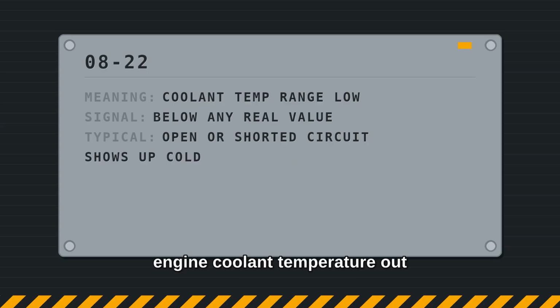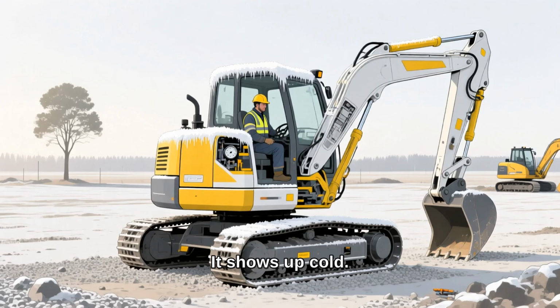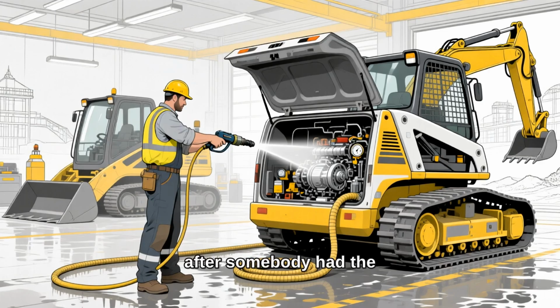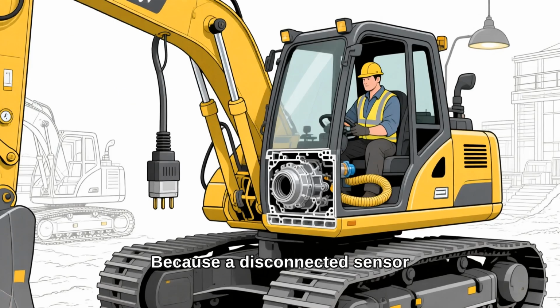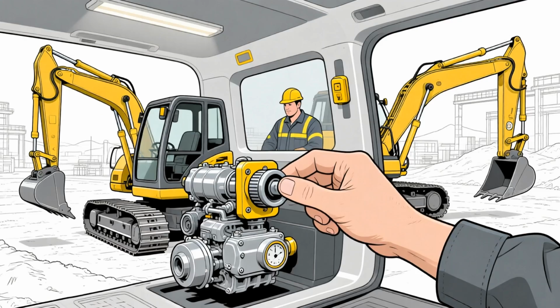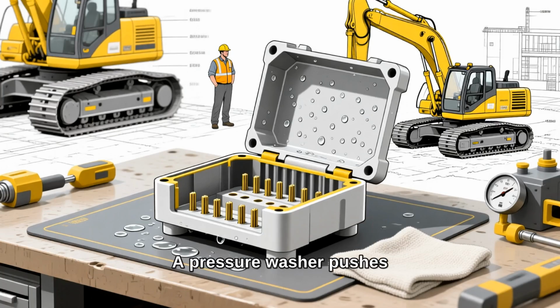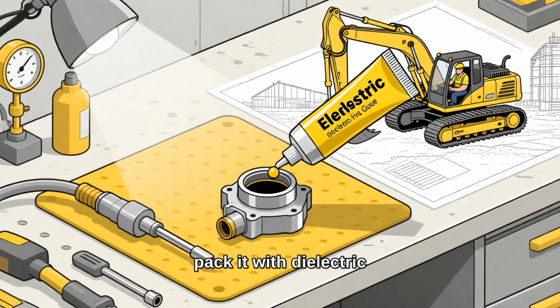Replacing the sensor first is the expensive habit, because a new sensor into a bad connector reads exactly the same. Now 822, engine coolant temperature out of range low. This one has a signature that gives it away. It shows up cold. First thing in the morning, on a machine that has never run hot in its life, and often the day after somebody had the panel apart, swapped a sensor, or pressure washed the engine bay. Because a disconnected sensor and a shorted one both send a value no real coolant temperature could make. So the check is physical before it's electrical. Is it plugged in, all the way, latched, not just resting? Then look for water. A pressure washer pushes moisture into connectors that were never built to be blasted. Dry it, pack it with dielectric grease, and run it. Half of these faults never come back.